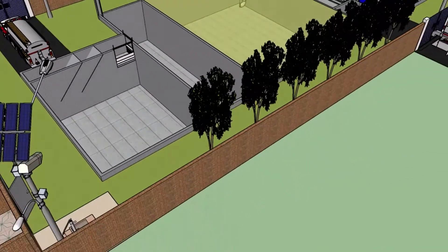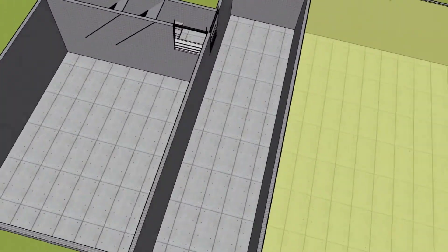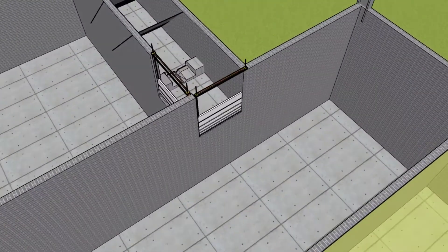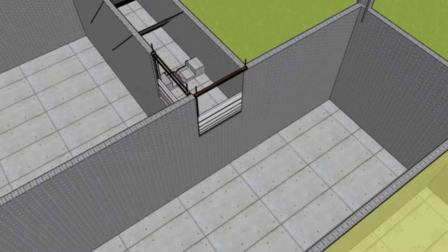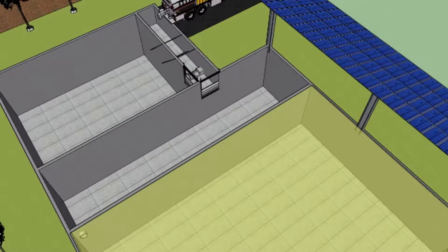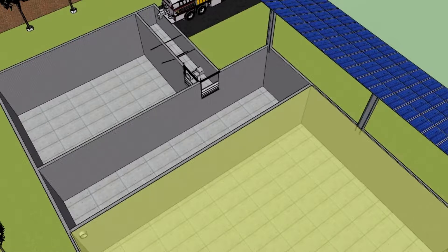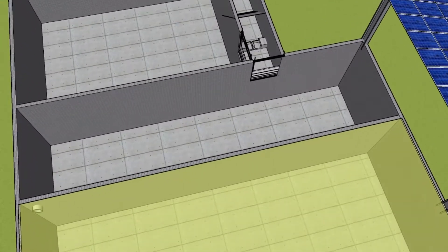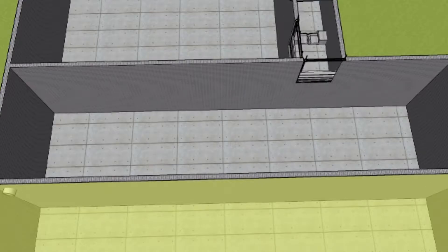The storage tank acts as a buffer. The equalization tank is required for the following reasons: it regulates the flow into the anaerobic tank and equalizes all contaminants. Biological water with a high-density population of microbes from the aerobic tank is introduced into the equalization tank to ensure reduction of ammonia in the septage.